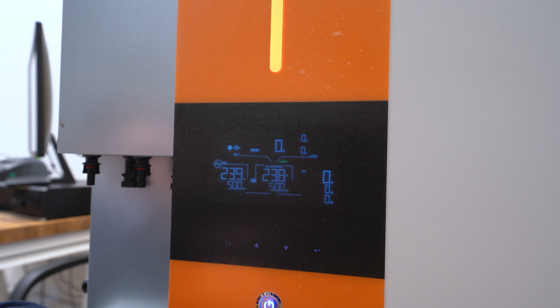This unit is made for the all-in-one system that we launched earlier this year. You can stack multiple 5 kilowatt batteries under the inverter, and one stack is made from one battery and one inverter, or two batteries and one inverter. If you don't want to use the lithium-ion batteries from the all-in-one unit, by changing the parameters in menu 5, you can connect other batteries like the Pylontech US2000 or US5000. The BMS works really well even with other lithium-ion batteries.